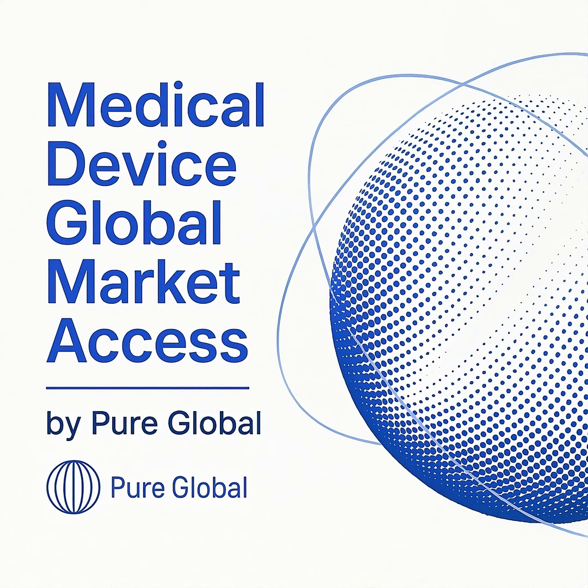For the United States, the two primary pathways are the 510(k) pre-market notification and the pre-market approval, or PMA. A 510(k) demonstrates that a device is substantially equivalent to a legally marketed predicate device, while a PMA is required for high-risk, Class 3 devices and demands extensive clinical data to prove safety and effectiveness.